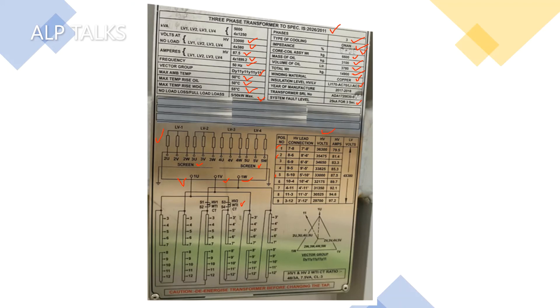The tapping voltage ranges from 36,300 to 29,700 volts, with different current values at each tap. The LV voltage is a fixed value: 4 x 380 V. Taps are used to adjust for voltage variation. Here is the vector group display — we can see there is a 30 degree displacement, as it is a DY11 transformer. The CT ratio is 48/3 amps, 7.5 VA, class 3. These things should be properly chosen for the CT to function properly. One caution: de-energize the transformer before changing the tap. As it is an off-circuit transformer, we should de-energize first, otherwise there is a chance of spark and fire due to arcing.